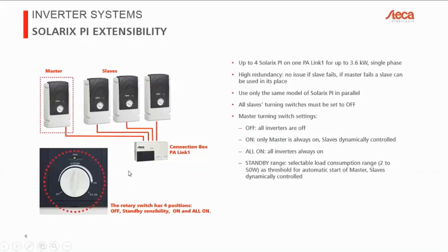Then there's the on position, what we have here on the right in the middle. This means that the master is always running. So that means that we always have 230 volts or 115 volts. These devices are also available in 115 volt versions. We can be sure that we basically always have our own microgrid running at all times. The nice thing is that the master is controlling the slave. So let's say that you're using more power than the master can deliver. The master will simply dynamically and automatically connect the slaves depending on how much energy you need. So you don't have to worry about that. The slaves are basically always in standby, and they are controlled automatically by the master. But if you have the master set to on, you can be sure that in some form there's always a clean, pure sine wave in your system.